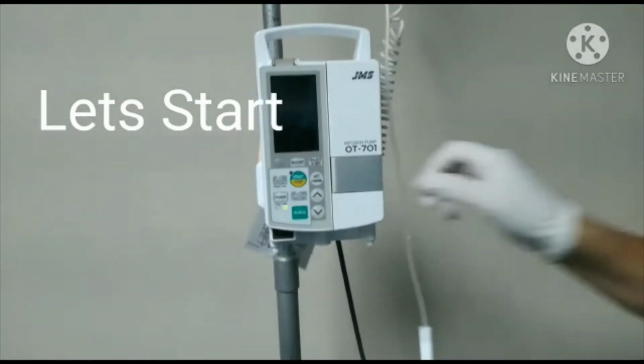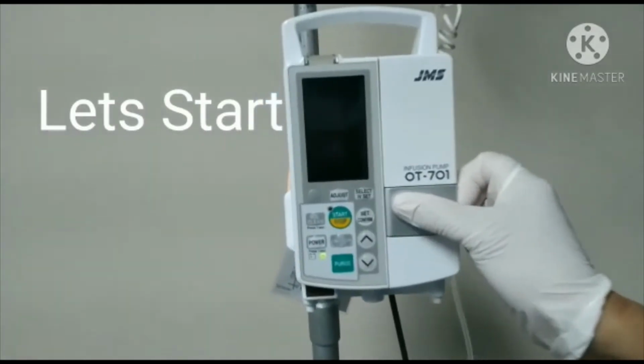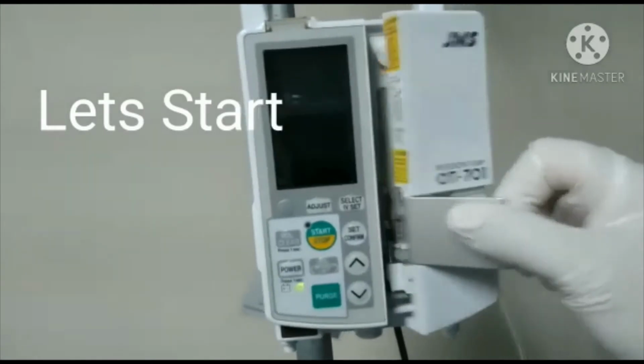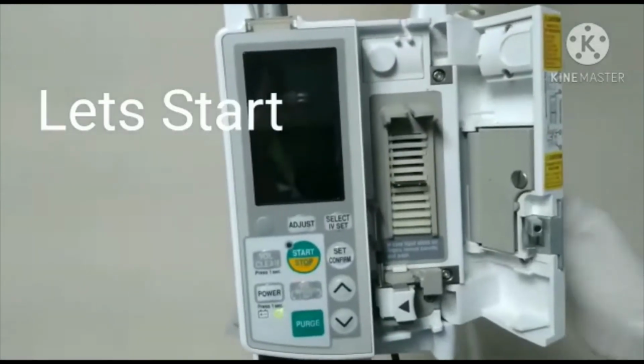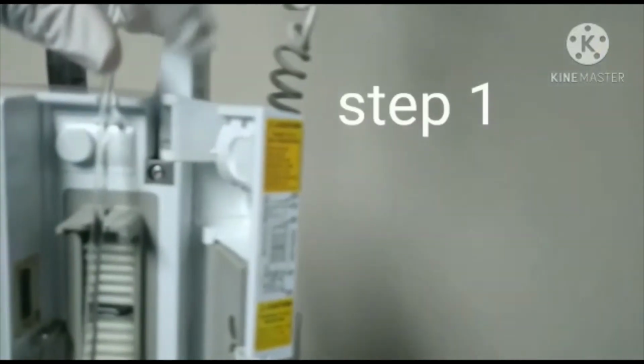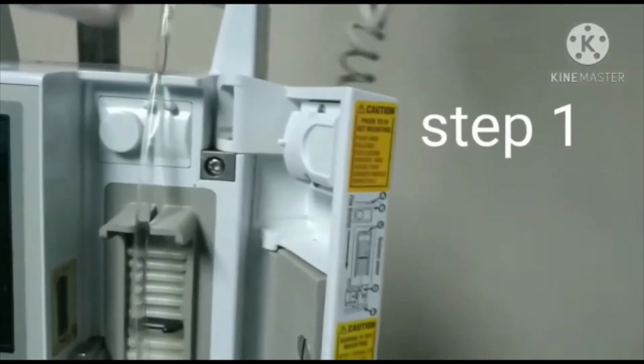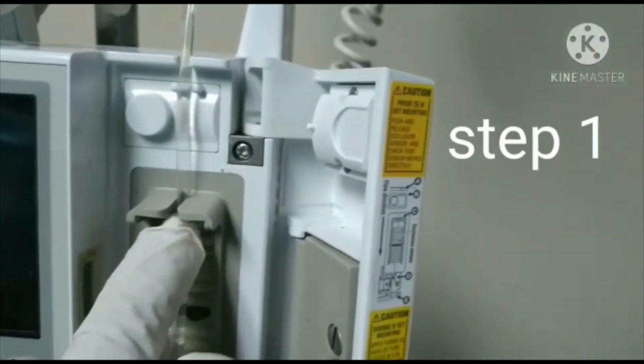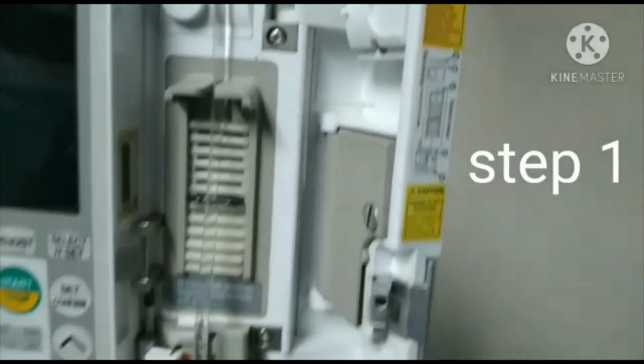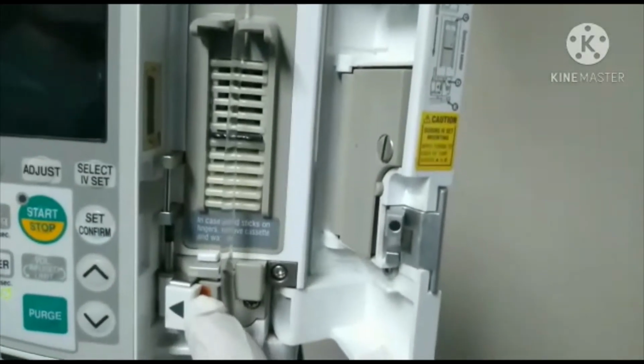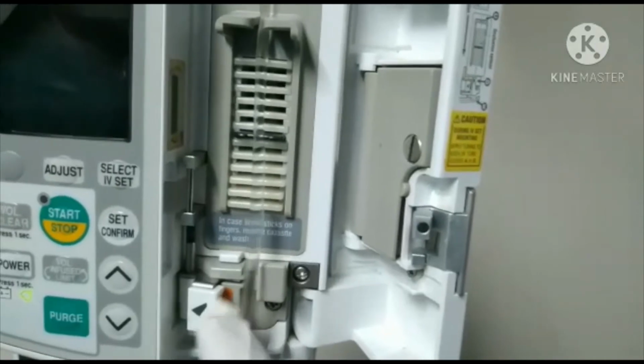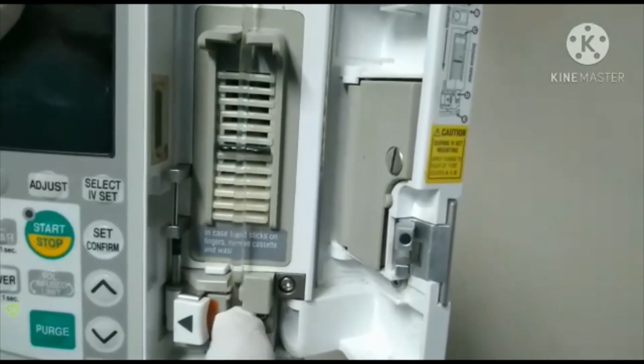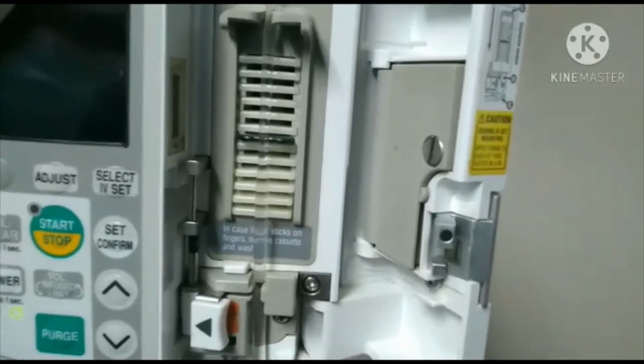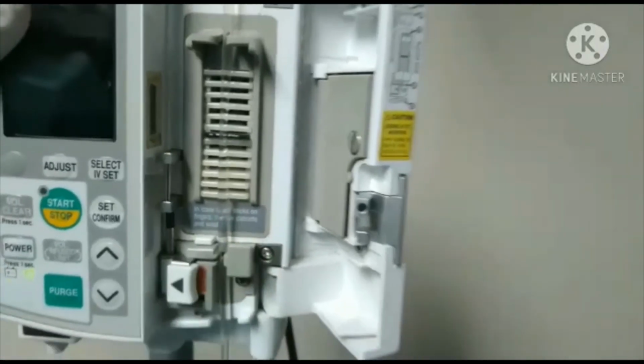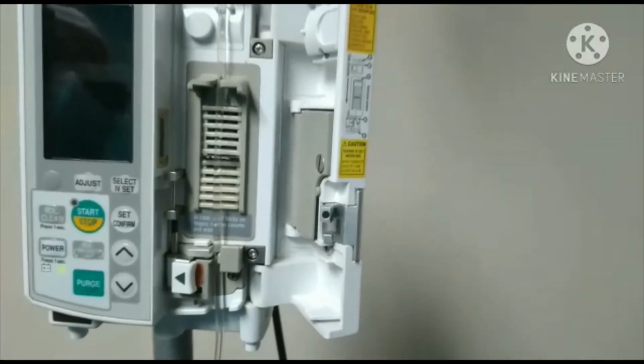Hang the fluid on the drip stand and open the door lever, where we will find the controlling portion of the pump. The tubing is first laced through the tube guide located at the upstream, then run through the guide for the air detector. It goes across the finger cassette, where the tubing passes in front of the occlusion sensor, finally passing through the tube clamp, which prevents free flow. And then its journey through the pump is complete at the downstream guide.